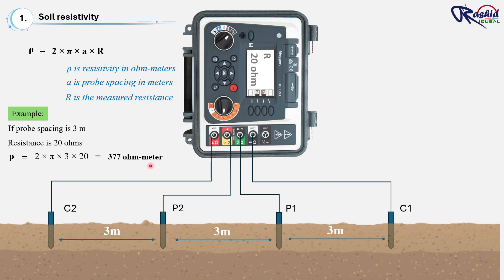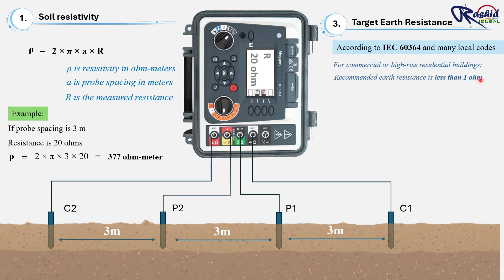So this is the resistivity of the soil. For most designs, we take the worst case, means highest value measured during the dry season. So in that soil, the resistance we get is 20 ohm. And according to IEC 60364 and many local codes, for commercial or high-rise buildings, the recommended earth resistance is less than 1 ohm. And for small buildings or residential villas, it should be up to 2 or less than 5 ohms. Once we obtain the soil resistivity value, we can select the most suitable earthing method for the project.